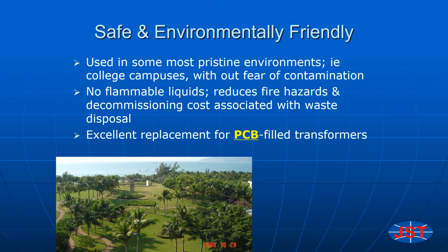Right. That's exactly why I showed the application guide. The big problem with the world these days is that everybody considers CapEx and not OpEx. So they make the judgment, well, we'll go with the VPI, and they try to use it in a harsh environment. But eventually the contaminants, as you say, get trapped in the VPI insulation system, and it will cause discharge. And discharge over time will wear down your insulation system until it eventually fails. What do they say, I forget what commercial it was, pay me now or pay me later. It's that type of thing. So when you look at OpEx, there's really nothing better than the cast resin, and you do get the long life out of it for sure.